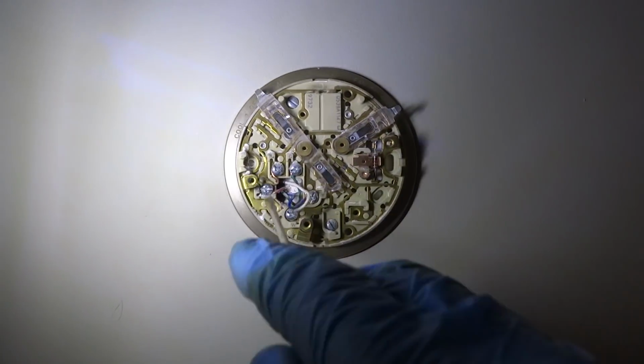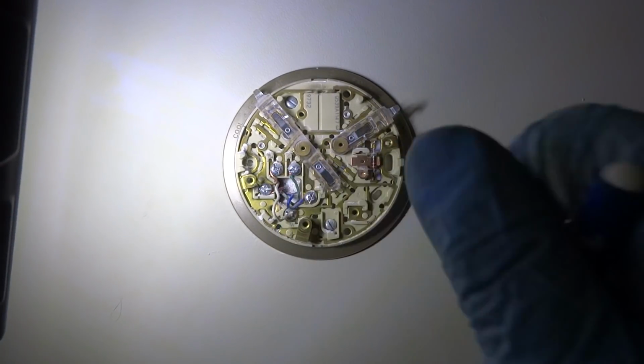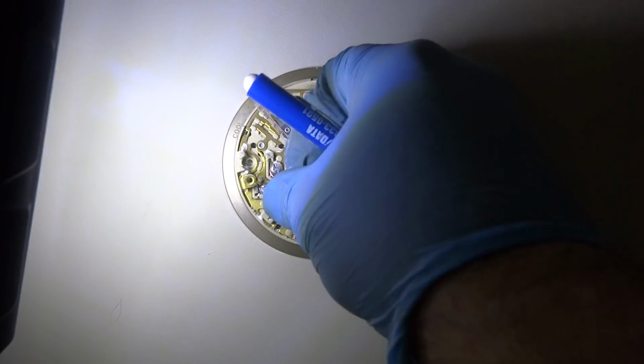That's the red wire coming in. It's loose. So you got the red, the red's coming in. It's jumping out the heat and the cooling, right, on the red. Then you got the white, which is for the heat. Then you got the green, which is the fan. And you got the yellow, which is the condenser. Alright, let's put it back and let's see if that works.